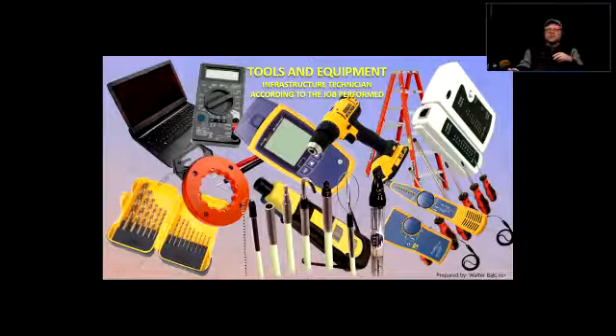And it's not going to be as, you can damage everything with anything, but it greatly lessens the chances of you damaging the wires while you're moving that fish tape inside the conduits with some already existing wires in it. Also, what I would suggest, there are different lubricants that you're going to put on that fish tape. Because if it's a 50, 60, 70 foot length of the conduit with some wires in it, you can only push that thing so far, and then the friction is going to work against you, right?